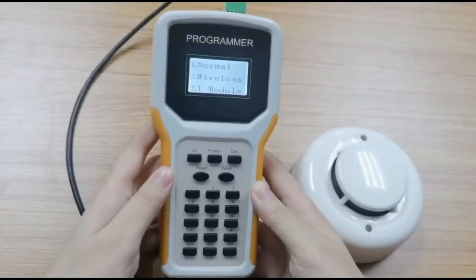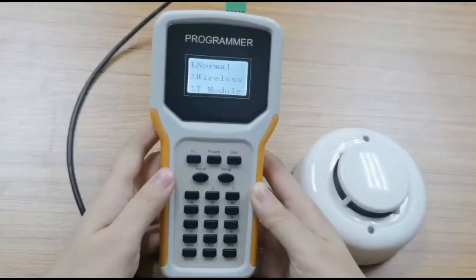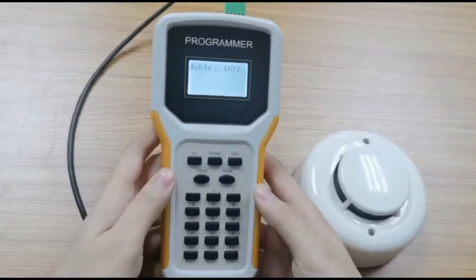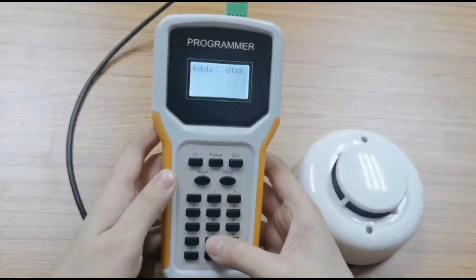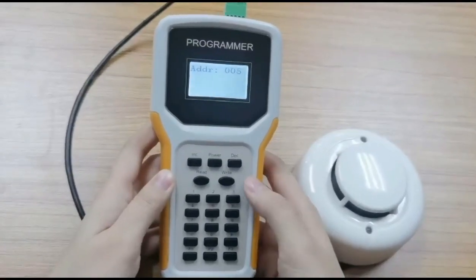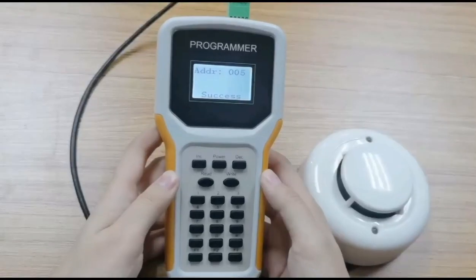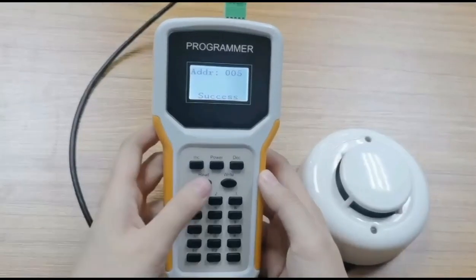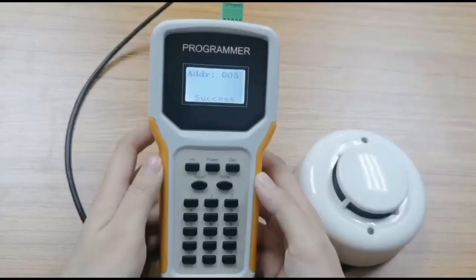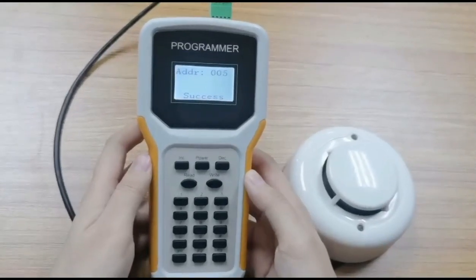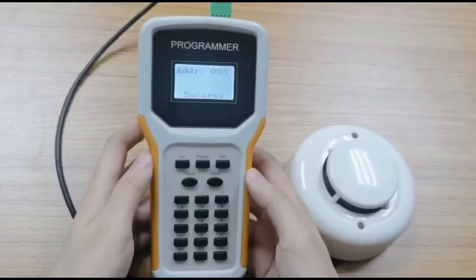After choosing number one, we can start to write the address. For example, we write zero zero five for this addressable device, and then press the write button to confirm. You can check the address again by pressing the read button. Our system has up to 250 addresses in each group, so the maximum address is 250.